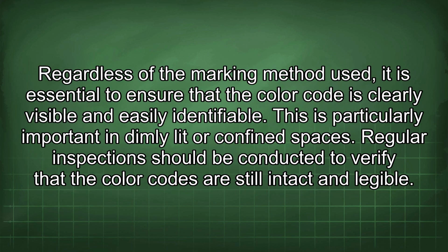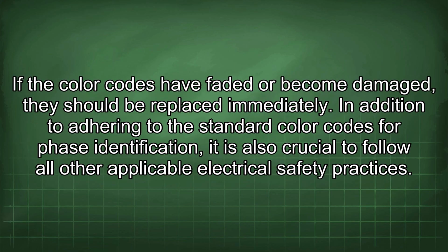Regardless of the marking method used, it is essential to ensure that the color code is clearly visible and easily identifiable. This is particularly important in dimly lit or confined spaces. Regular inspections should be conducted to verify that the color codes are still intact and legible. If the color codes have faded or become damaged, they should be replaced immediately.